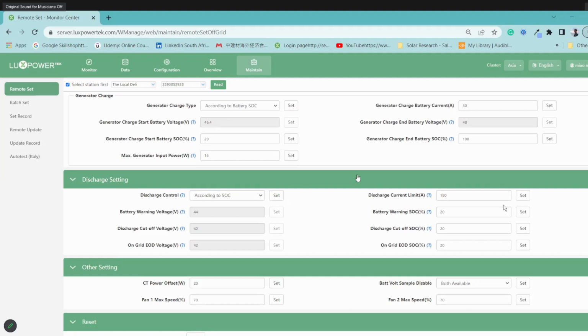Yeah, what I've experienced: let's say I've got a load of 1000 watts being pulled on the system, and I can see the battery voltage is 48.8. Then if someone switches on a kettle, suddenly the voltage drops to around 47.5, which is below the setting we made, so the system kicks out the battery and goes on AC. But as soon as that kettle has finished boiling and the load has reduced, you'll see the voltage pick back up to 48.8. So I'm wondering how one gets around that, because it's not actually a true reflection of the battery state.